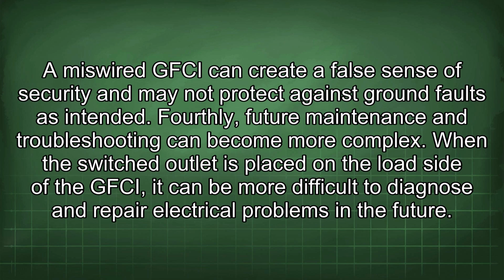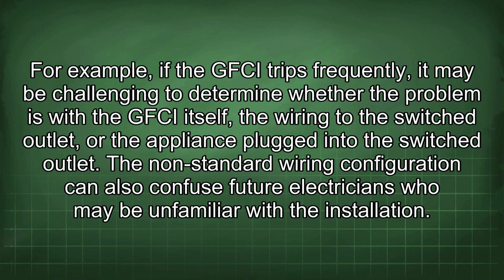Fourthly, future maintenance and troubleshooting can become more complex. When the switched outlet is placed on the load side of the GFCI, it can be more difficult to diagnose and repair electrical problems in the future. For example, if the GFCI trips frequently, it may be challenging to determine whether the problem is with the GFCI itself, the wiring to the switched outlet, or the appliance plugged into the switched outlet. The non-standard wiring configuration can also confuse future electricians who may be unfamiliar with the installation.